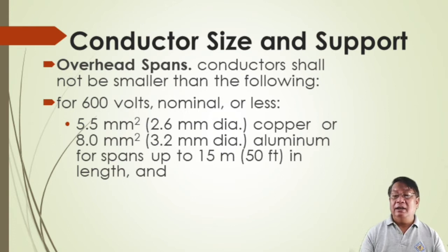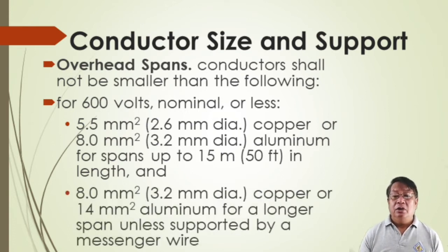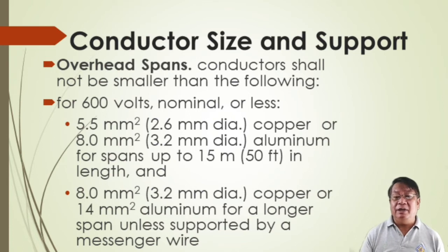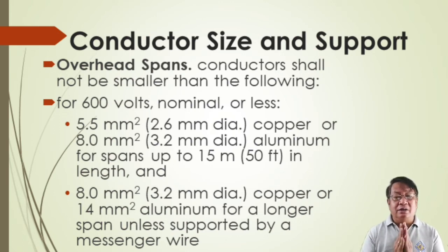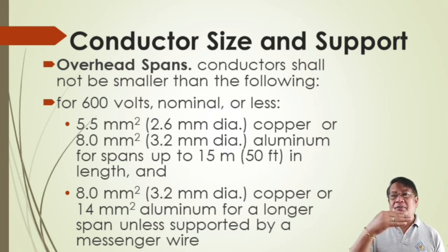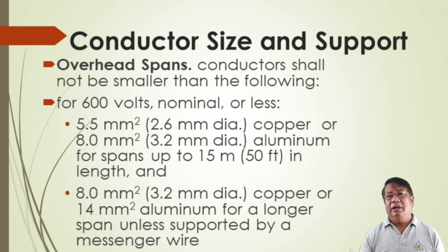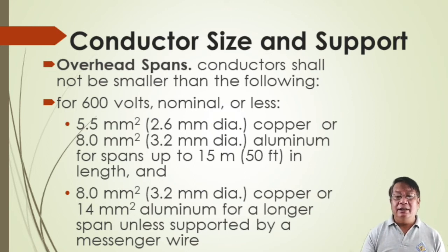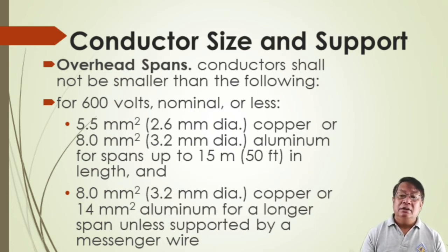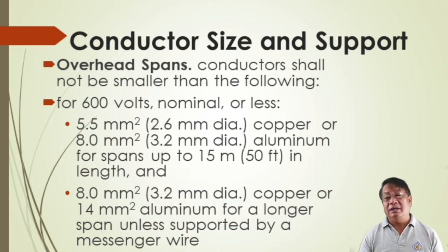For spans longer than 15 meters or 50 feet, use 8.0 mm² copper or 14 mm² aluminum unless supported by a messenger wire. A messenger wire is a tie wire or solid wire that supports the conductor within a longer span. For more than 15 meters, use 8.0 mm² copper or 14 mm² aluminum.